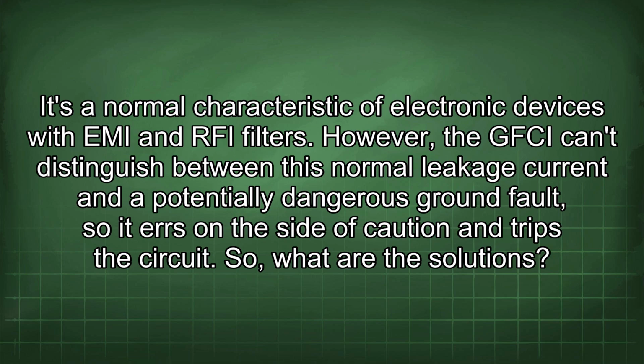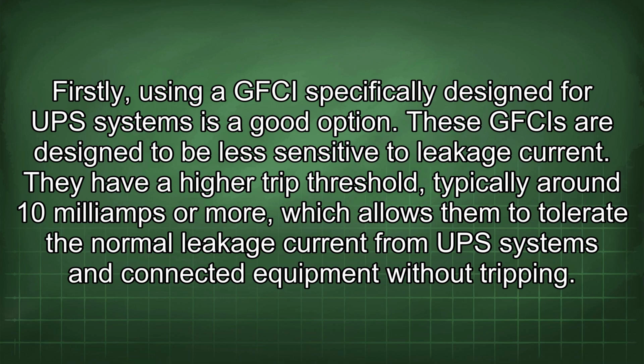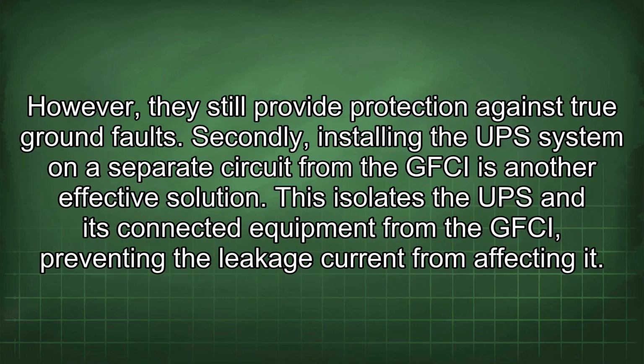So, what are the solutions? Firstly, using a GFCI specifically designed for UPS systems is a good option. These GFCIs are designed to be less sensitive to leakage current. They have a higher trip threshold, typically around 10 mA or more, which allows them to tolerate the normal leakage current from UPS systems and connected equipment without tripping. However, they still provide protection against true ground faults.